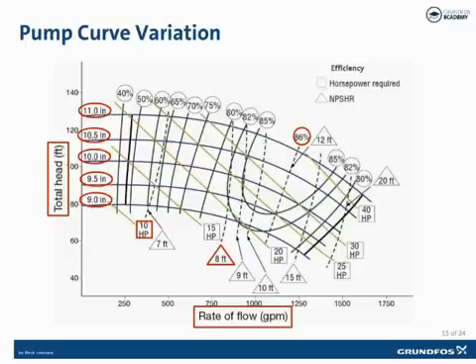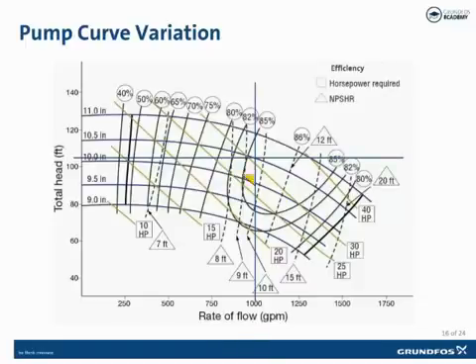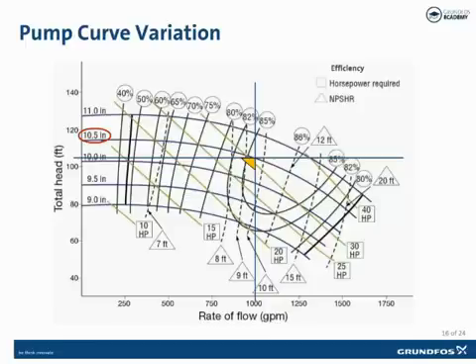The impeller is always cut to the next largest one-eighth inch increment. After the system designer has determined the head requirement at design flow, a suitable pump is selected. For this example, we'll use a desired flow of 1,000 gallons per minute at 103 feet of head, shown as a triangle at the intersection of design flow and design head. The actual impeller shipped with this pump will be a 10.5-inch impeller. At this design point, the efficiency would be 85.2%, the brake horsepower required would be 30.1 BHP, and the net positive suction head required would be 9.5 feet.